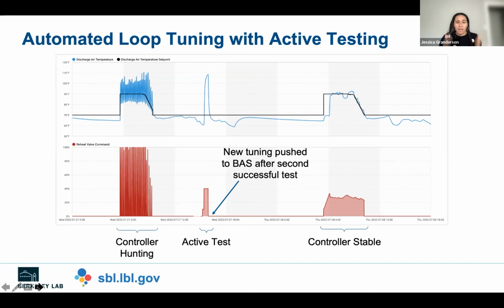So what we did was then, what you see in the middle of the plot, implement a routine to conduct active testing, identify new tuning parameters for that PID controller. We push them to the BAS. And then on the rightmost portion of the plot, you see the after effect. We've stabilized this controller. The valve command is more steadily modulating throughout the day. And on the top plot in the blue and black, the actual discharge air temperature is better tracking the set point.